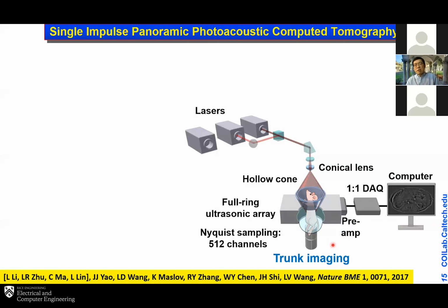Preamplification is very important because the signal, especially if you want to image deep, is very weak, and you want to conserve every bit of signal to noise ratio. And so you want to amplify your signal as soon as you get the electronic signal, instead of waiting for cable noise to creep in and reduce your SNR. It's very hard to retrieve the lost signal to noise ratio. We use a one-to-one data acquisition, and so with a single laser shot, we can capture the image, again within tens of microseconds. Then we can repeat our laser pulse to get the next 2D image.